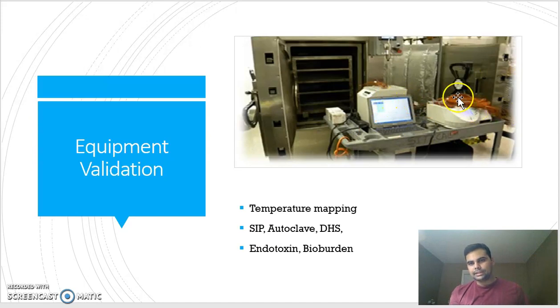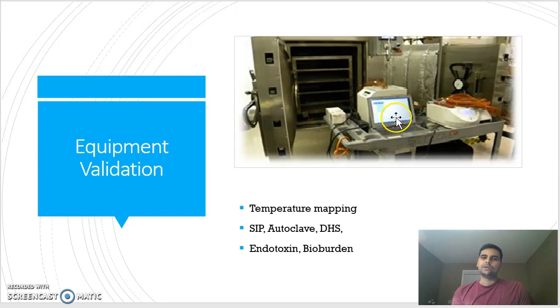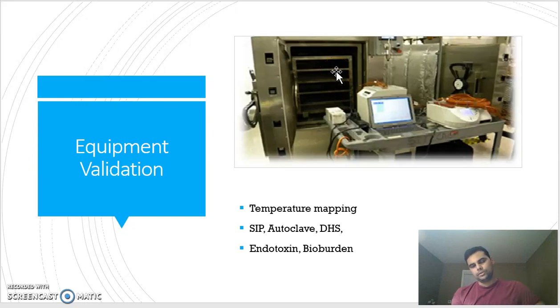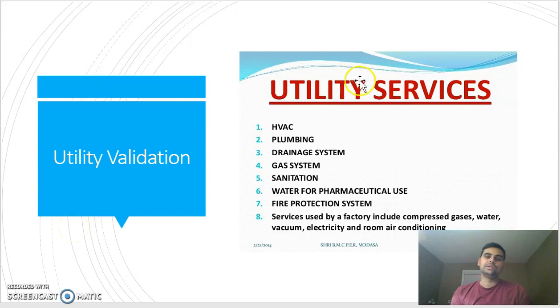To validate an autoclave, you use a data logger and thermocouples — temperature-sensing devices — that you place throughout the entire chamber to see the temperature profile at different locations and record the entire cycle. This gives you assurance that everything is running fine and you have a good picture of your autoclave's performance. Equipment validation activities include temperature mapping, SIP, autoclave, and DHS testing, as well as endotoxin and bioburden assessments.